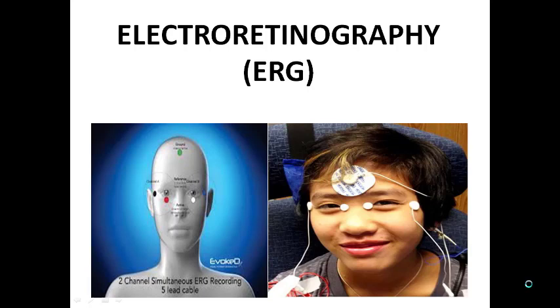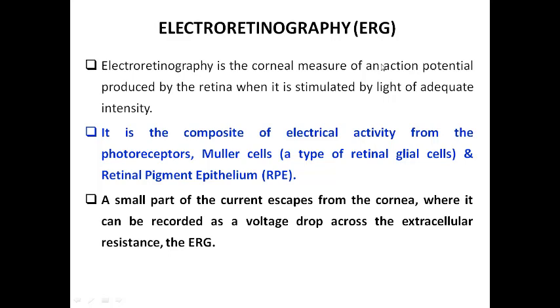Today we are going to discuss two topics of biomedical instruments related to the ophthalmology field. The first one is electro-retinography, in short ERG. Electro-retinography is used to measure the electrical potential produced by the retina when it is stimulated by light of adequate energy. The electrical activity of the retina is composed of activity from photoreceptors, Müller cells, and retinal pigment epithelium layers. A small part of the current escapes from the cornea where it can be recorded as a voltage drop across the extracellular resistance, named as ERG.